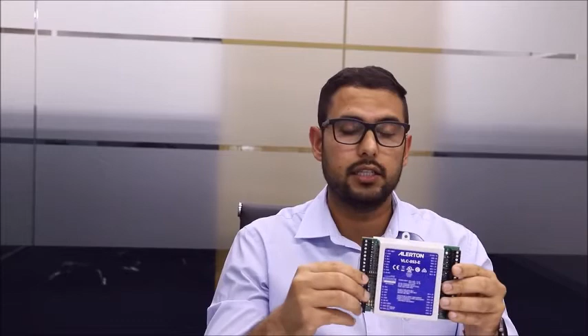So what it does is, DDC code represents a software program that reads the physical values out there. That can be a temperature input, a pressure, a flow rate, or any other input that comes with the project, and interprets it, does its own calculation, and based on our functional programming, it decides what output it needs to give. And the end result needs to be energy efficiency, smooth flow of processes, and fault monitoring.